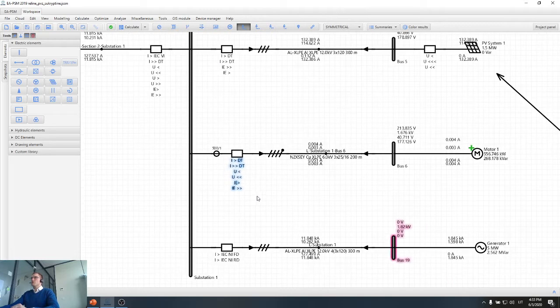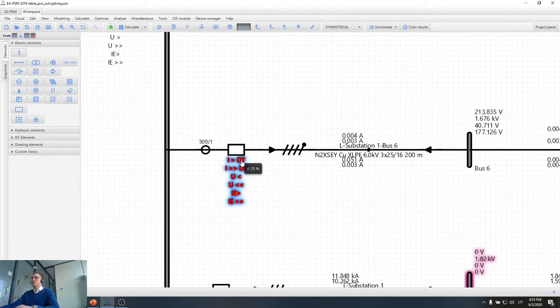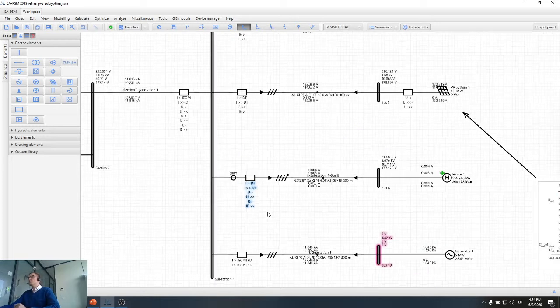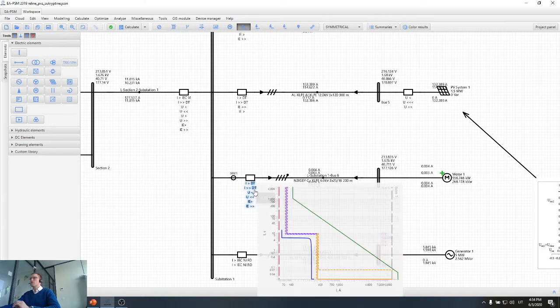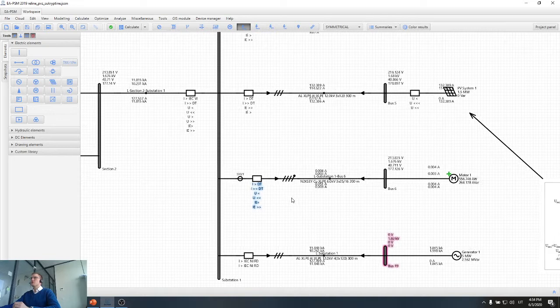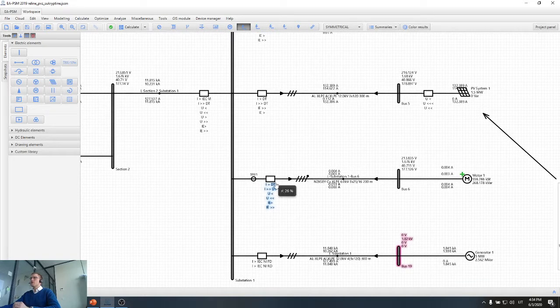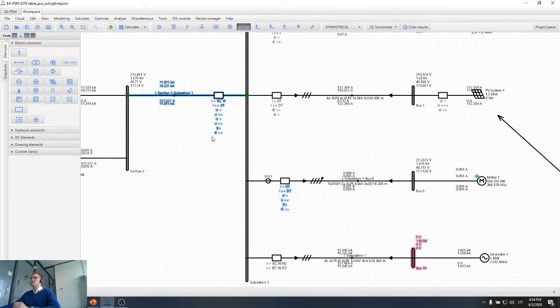So basically, for this motor I have provided a numerical relay with almost six functionalities: overcurrent, undervoltage, and also earth fault current. In software it is possible to add not the protection device itself, but only the functionalities of the protection devices. You provide the functionalities, and these can be used in any other relay. You can provide these functions by adding the data you have set to the relay, and it will operate according to the user's needs.